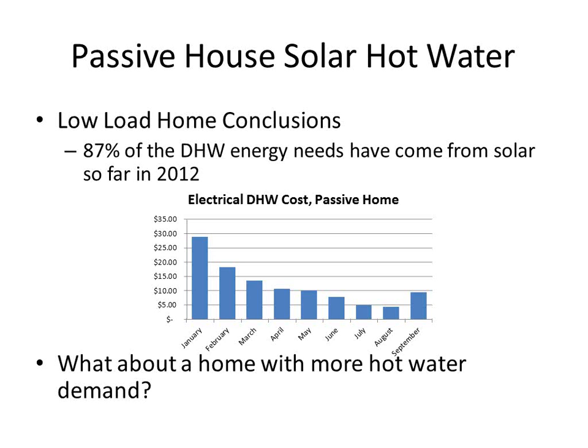When she's putting water in at 160 degrees, even if she has a day or two where she doesn't use it, it'll only drop 10 to 15 degrees a day, so she'll continue to have hot water replenished with 160 degree water. The mixing valve would instead dump in water at 130 to 140 degrees, so if she has a couple days without use, it could cool down to the point of being uncomfortable, and she'd want the electric hot water heater on. By removing the mixing valve in between the two, it allows truly unassisted operation throughout the summer months to become much more viable.